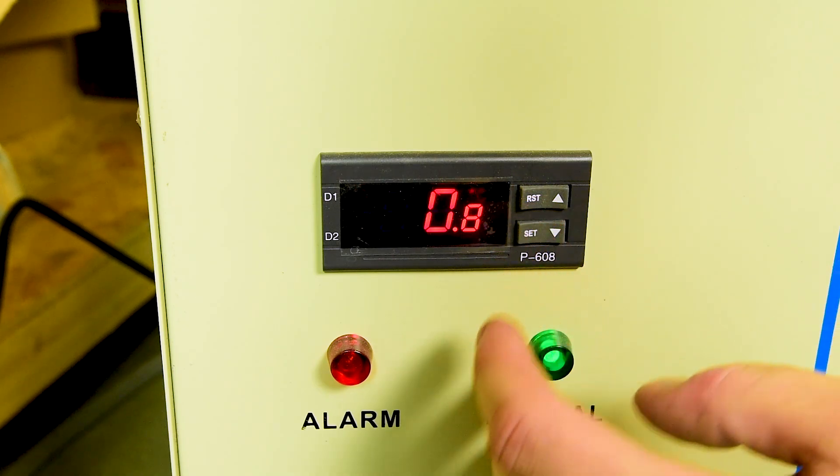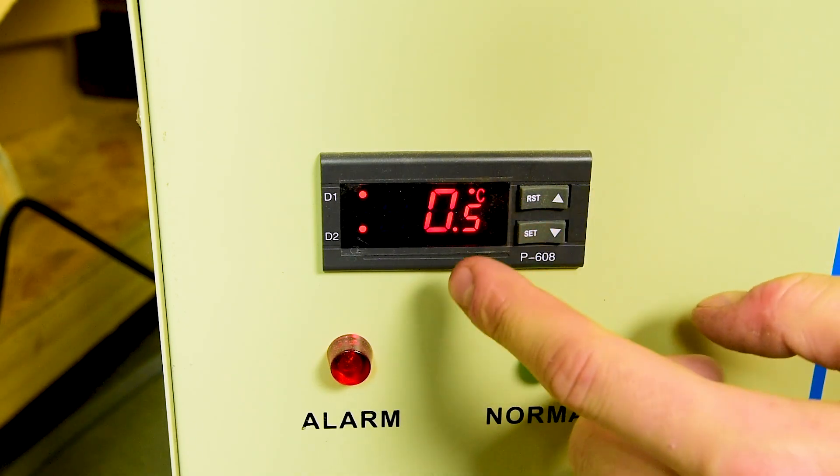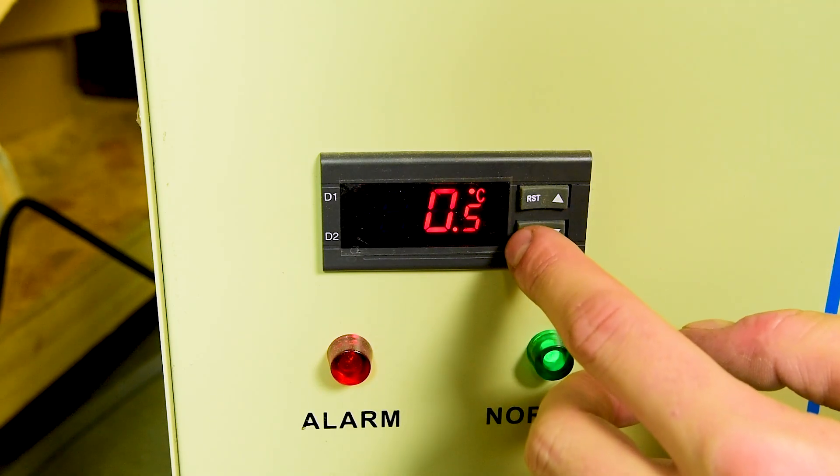F2 is how much temperature difference we're allowing so I'm going to say to hold within half degrees plus or minus half a degree of 15 degrees is where I want this to keep the water temperature.